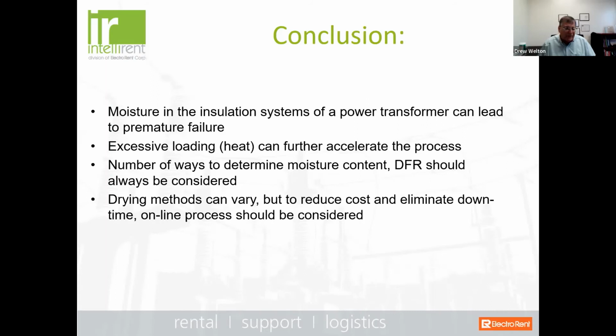Ambient temperature typically does not, unless you have a fairly inadequate cooling system, such as your radiator systems. But yes, ambient temperature can play a part in heat, because when you have a lot of ambient temperature that's running very hot, that means your loads are typically higher. You've got air conditioning, you've got all these conditions that make the loading that much higher.